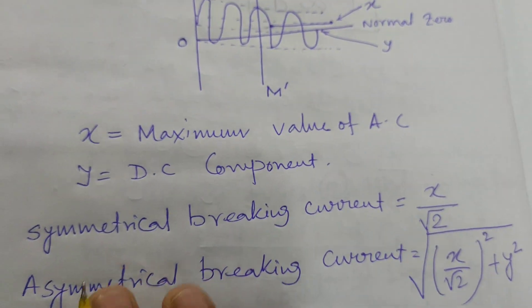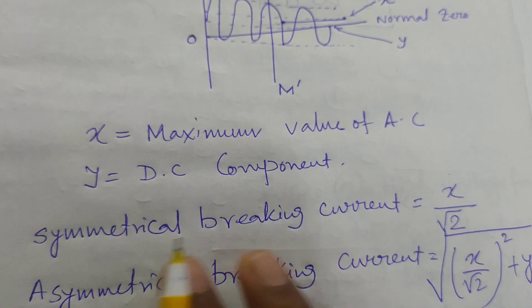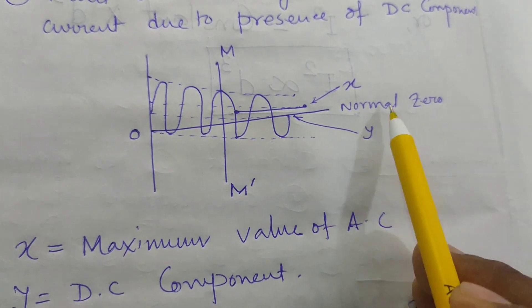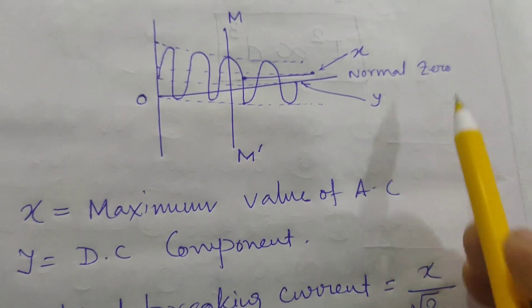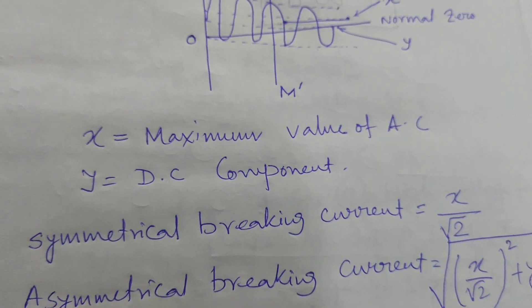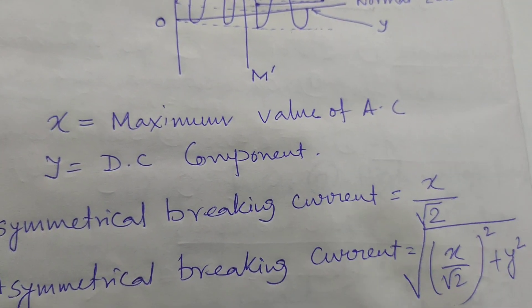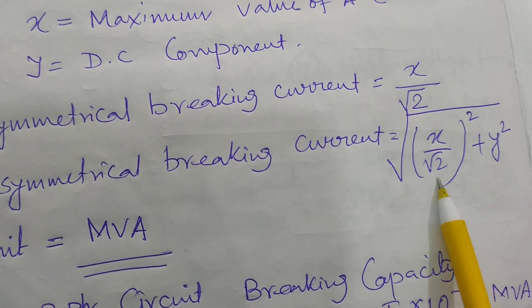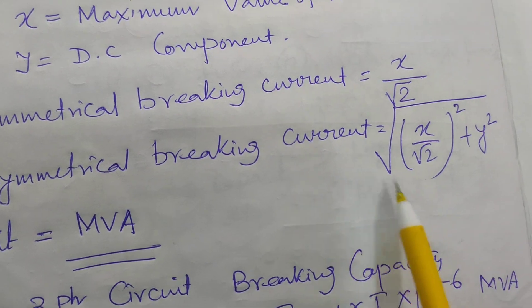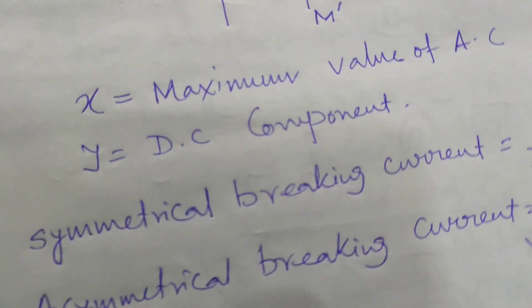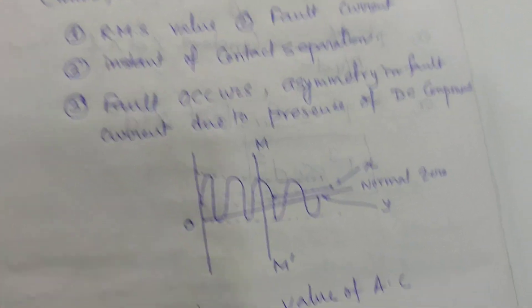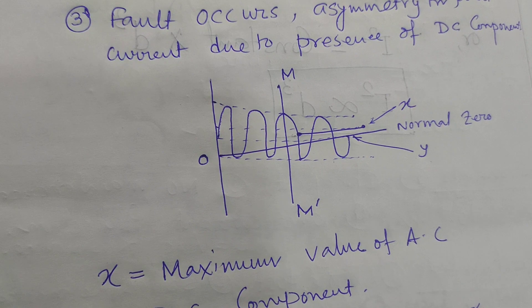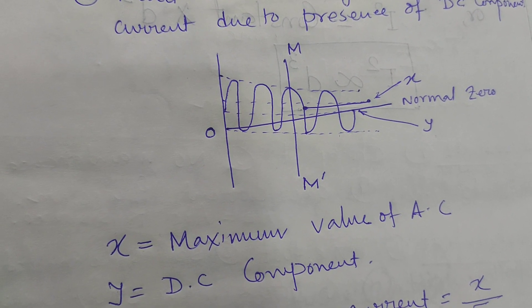The Symmetrical Breaking Current: if X is the maximum value of the AC component and Y is the DC component, then Symmetrical Breaking Current equals X divided by root 2. The Asymmetrical Breaking Current equals the square root of (X/√2)² plus Y². The breaking capacity is always stated as the RMS value of the fault current at the instant of contact separation.